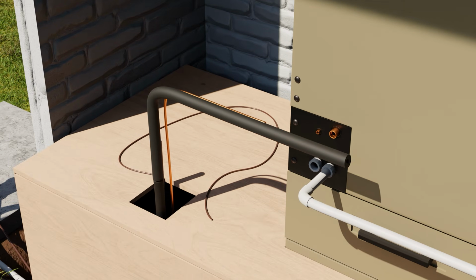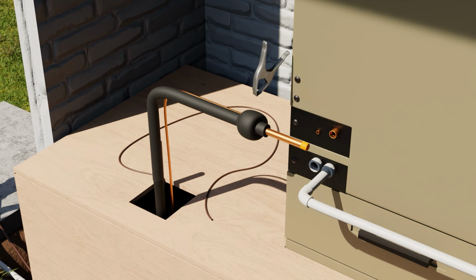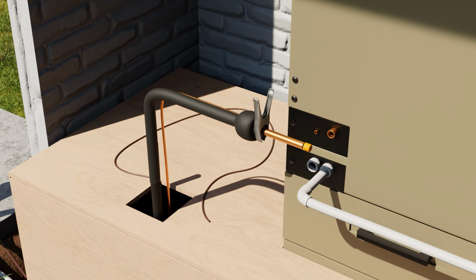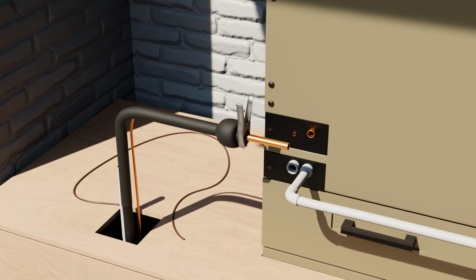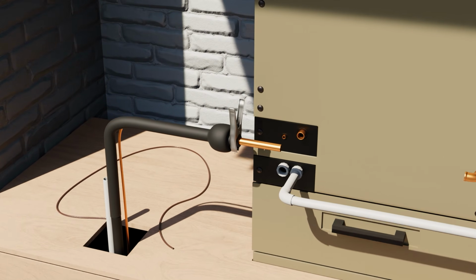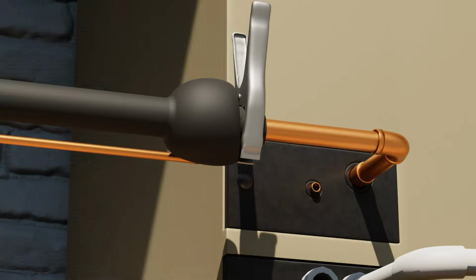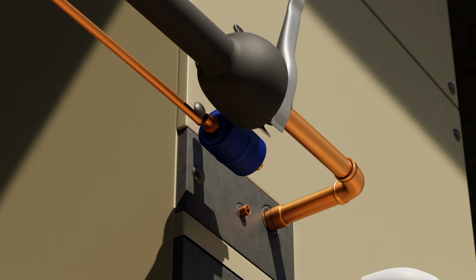We use inexpensive metal clamps to hold back the tubing insulation so that we can work without damaging it. In some cases, if the tubing insulation is close, you may need to put a wet rag around the tubing insulation to prevent yourself from damaging it while you braze. Here we're showing using fittings to make the final connections. In some cases, you can do this just by bending the tubing with a bender.